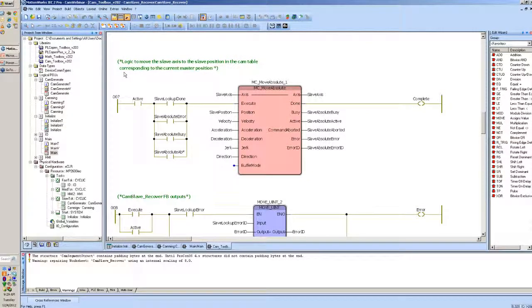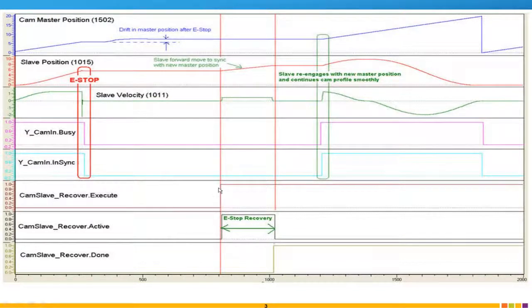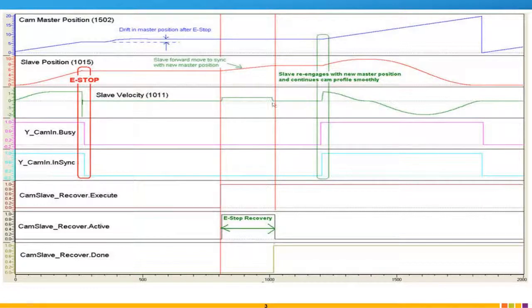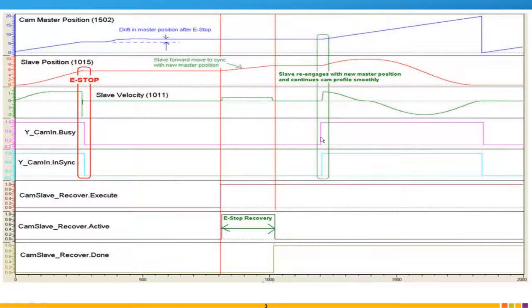Back to our little graph here. Here's our e-stop recovery. We execute that cam slave recovered. It looks up in the table what the slave position should be. It does an absolute move to that slave position. And now we are back in sync as far as the master and slave position go. And then we can re-execute our y cam in and everything is back to normal.